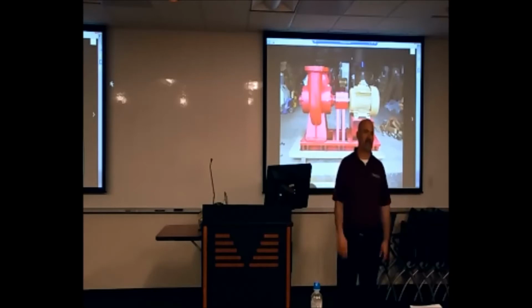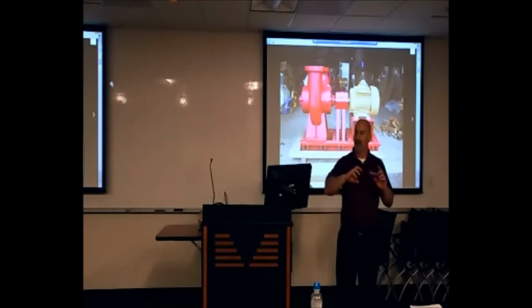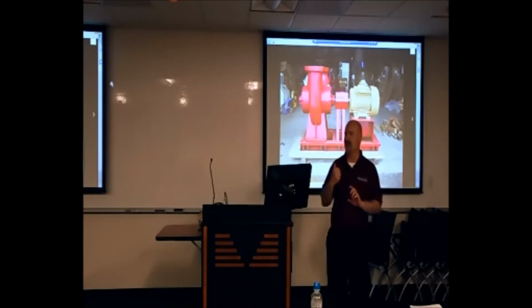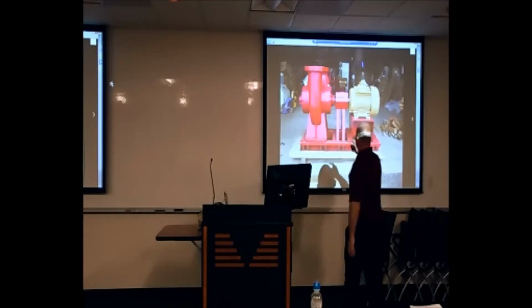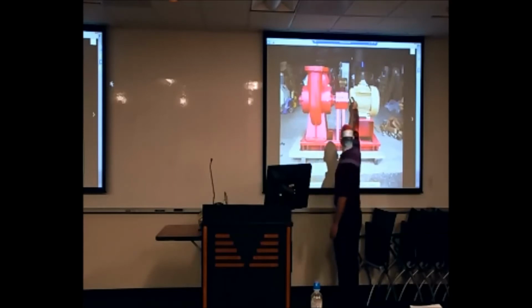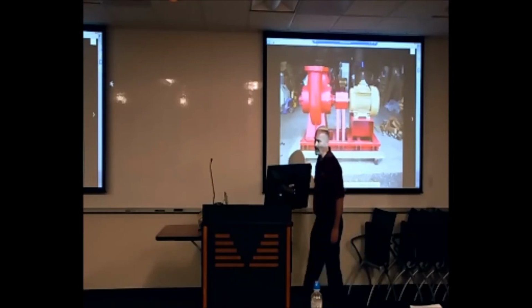As soon as it starts to rain and you get some water on the shaft, it's going to migrate its way right into the bearing. With the water slinger there, centrifugal action causes it to fling the water off that pump shaft and get it away from the bearing before it gets in there. You can actually see the Baldor one in this picture. It's basically just right there, so if there's any water in there, it'll fly off and blow it away.